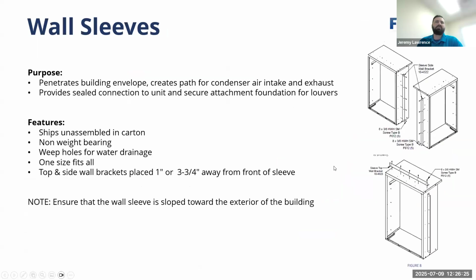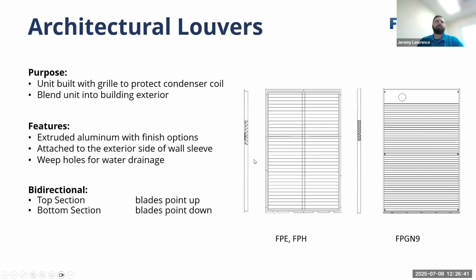Sleeves come shipped flat, much smaller than the Eco Series sleeves. They don't take the weight of the unit, but they're really meant just to seal that gap between the wall and the unit. Same louvers for the condenser air exchange. The only change here is that the FPG N9, which is the natural gas 95% efficient unit, has the exhaust hole penetration right there, so that it vents out through the grill as well.